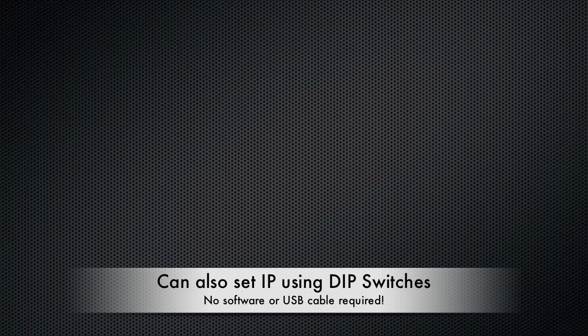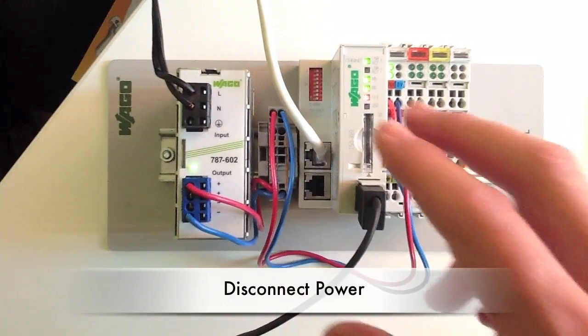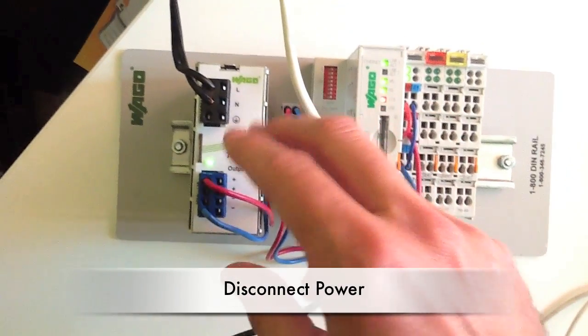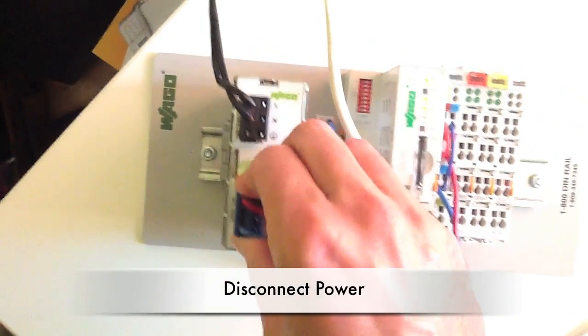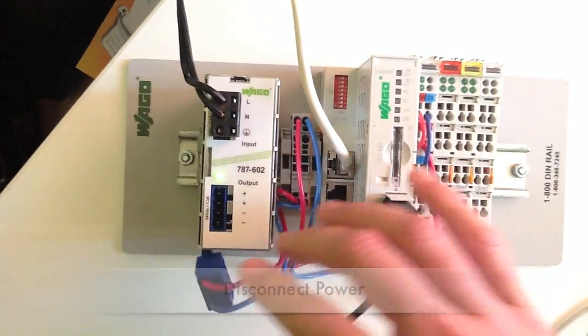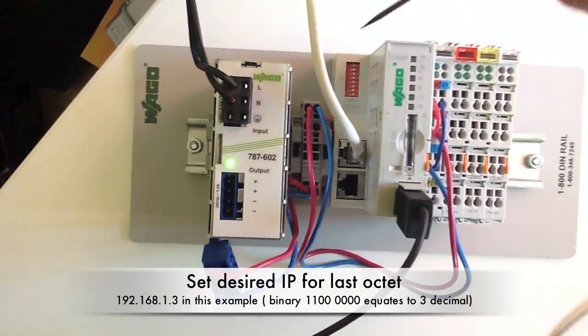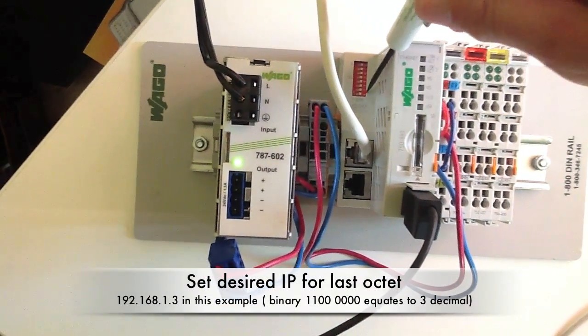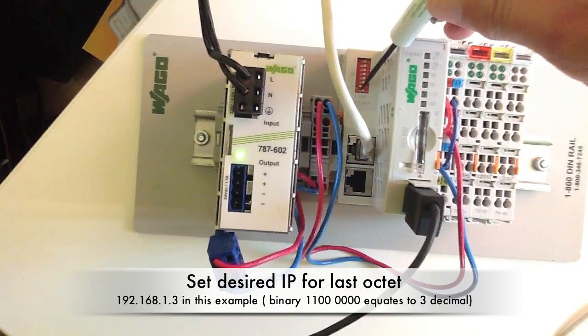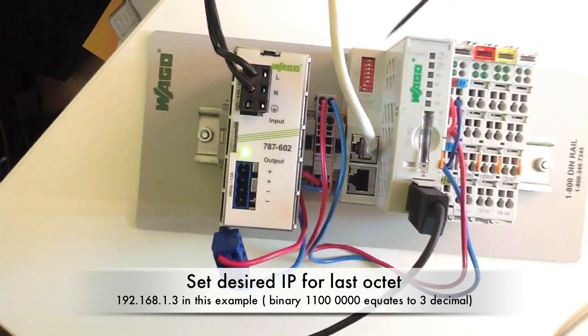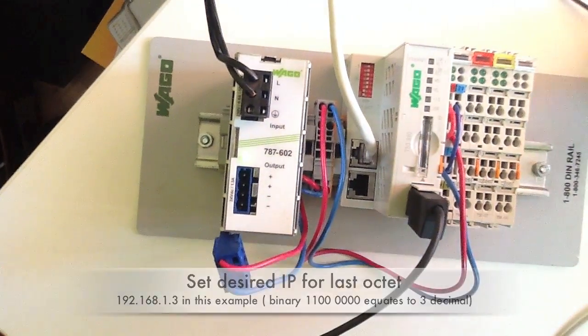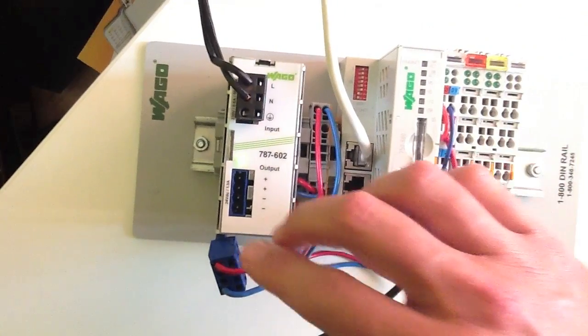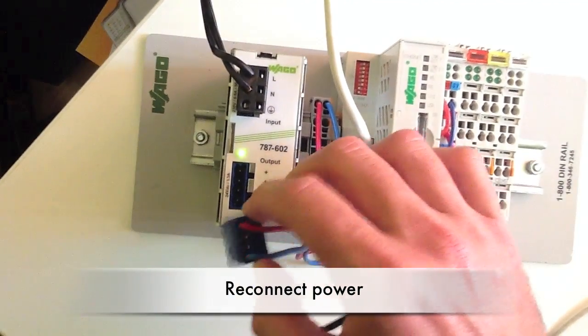So lastly, one of the big advantages of the 750 880 series are the DIP switches. So if you just remove power, you can actually set the IP address just using a screwdriver and setting the last octet to whatever you want to set the IP to. And this doesn't require any software at all to configure it.